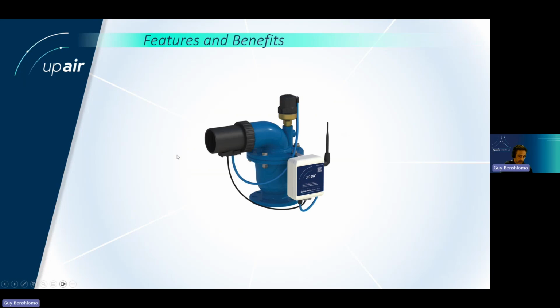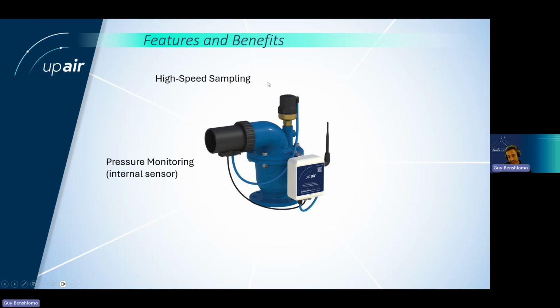And you can think together with us about which solution we can bring with this device that has pressure monitoring every 10 seconds as the default, but we can change it. If we detect an abnormality, or we detect that the valve is moving, tilted or tampered, we can activate fast sampling that goes up to 100 hertz, that is 100 times in 1 second. And in this way, we can detect water hammer if necessary.